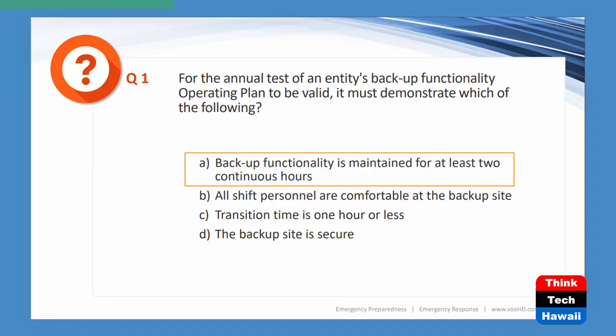And to fully transition, that's the important thing. So it's 2 hours to fully transition, but that means it's 2 hours to leave the control center, go to the backup site physically, get in, log in, get everything set up, and be fully transitioned, meaning that you have been able to actually go there and transfer control over, right? That means all your vital functions, communications, EMS control, and all the systems you need to actually operate the system. That's what they mean by fully transitioned in 2 hours. It doesn't mean you have 2 hours to drive there, because it's going to take you some more time to get in there and get set up and start running. So that is one of the questions.